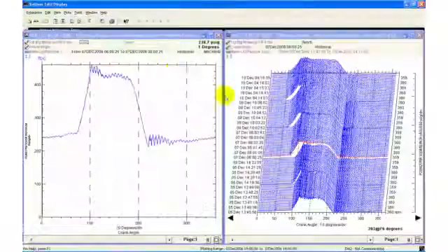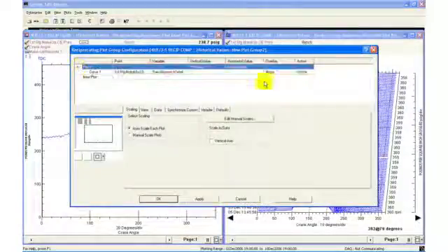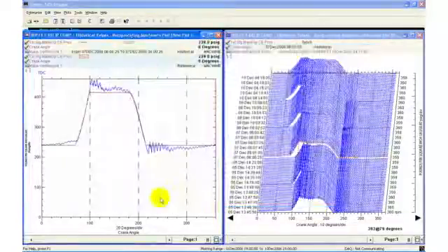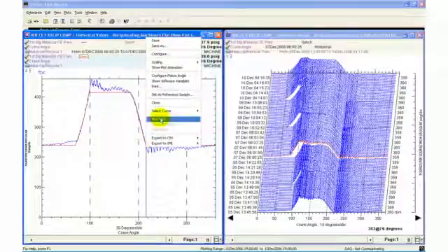Putting it all together, the visualization tools in System 1 software, combined with accurate data from our transducers, provide dramatic insight into valve condition and compressor loading. A comprehensive suite of graphs for cylinder pressure let our customers quickly diagnose cylinder leaks and manage the condition until an optimal time to repair is reached.